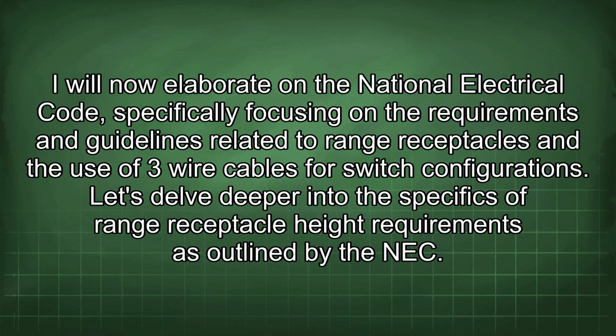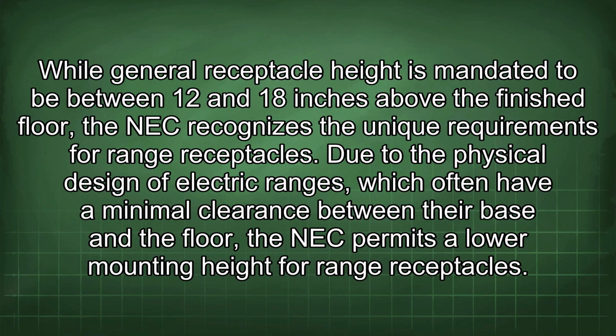I will now elaborate on the National Electrical Code, specifically focusing on the requirements and guidelines related to range receptacles and the use of 3-wire cables for switch configurations. Let's delve deeper into the specifics of range receptacle height requirements as outlined by the NEC. While general receptacle height is mandated to be between 12 and 18 inches above the finished floor, the NEC recognizes the unique requirements for range receptacles.